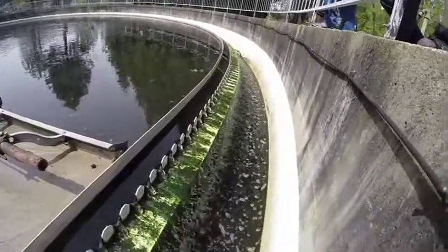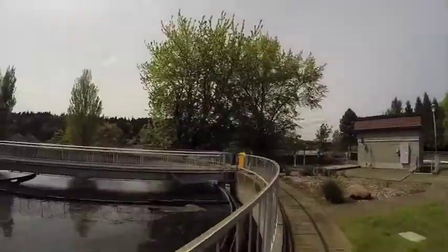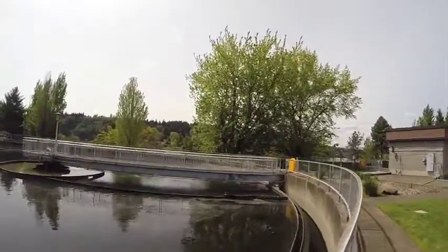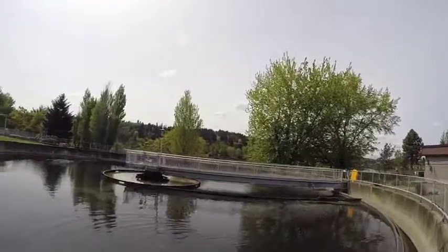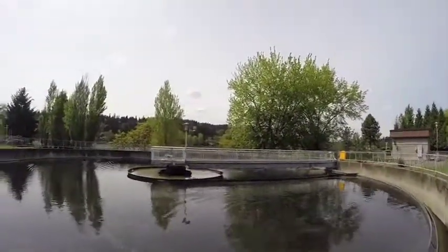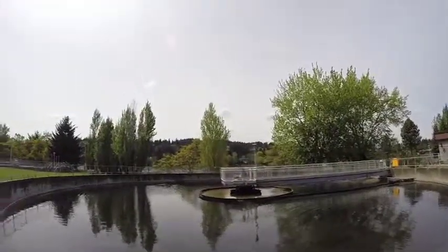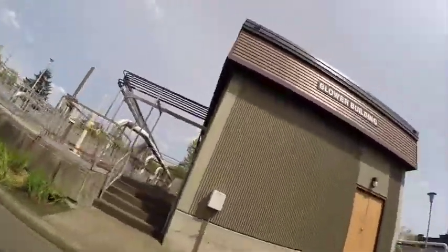See the algae. Yeah. How I control that is, we have sodium hypochlorite here, and so when I have a tank back there, I take this offline and spray this down with that bleach, and it'll take that right off. I've only done it one time so far this year because it's been so wet. But we'll probably get to it next week, and that'll be completely cured.